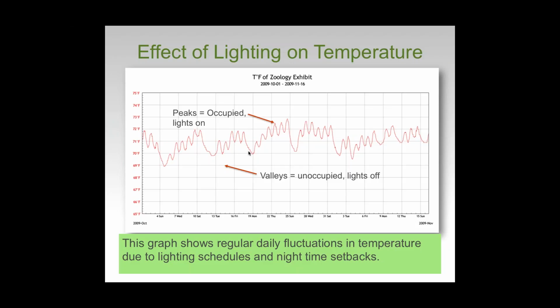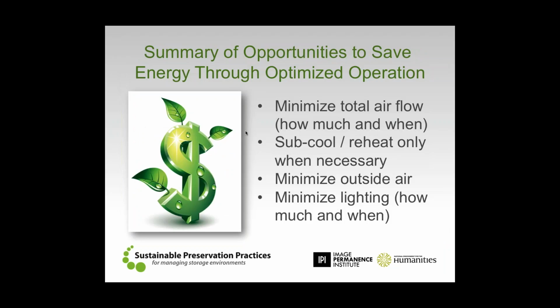And if those are turned on all the time, imagine that instead of having these valleys where the temperature cooled down a little bit, we'd be running at the top side of this all the time and paying for it, not only in terms of preservation quality, we'd lose a little bit there, but also in terms of the total amount of cooling that the system has to perform. So the big ones at the end of the day, when we're thinking about what these strategies need to be: we need to try and minimize that total airflow, whether it's through a shutdown or slowing down the fan. We need to try and subcool and reheat only when it is absolutely necessary, looking at that dehumidification operation.